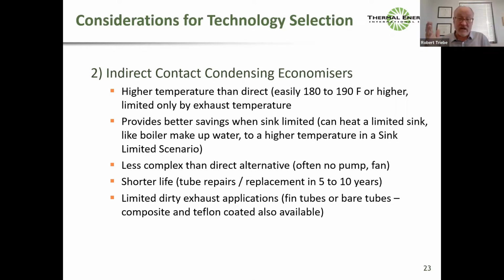Classic example, boiler makeup water. If I've got a huge amount of waste heat and only a small boiler makeup water load, then my savings will be dictated by how hot I make that boiler makeup water. My savings will not be dictated by my source. My source, I've got more source than I can possibly use. My savings will be dictated by the temperature I can bring my sink to. But in the case of having more sink than source, my savings are dictated by how cold I can make the source. So source and sink limited, different design considerations, and hopefully it becomes clear as we move through this.